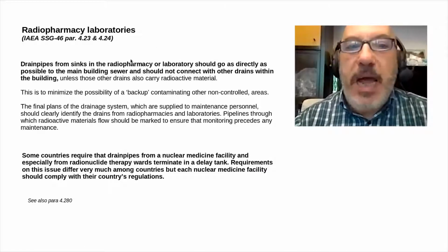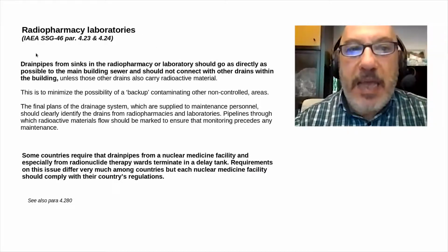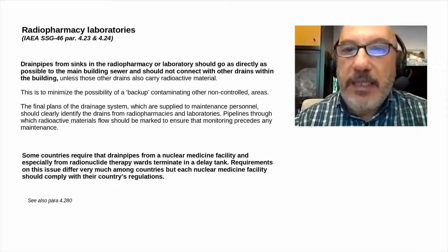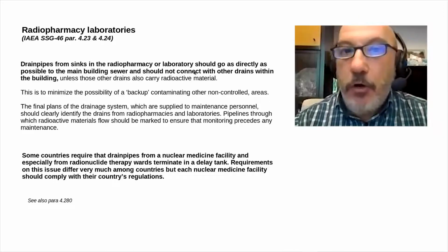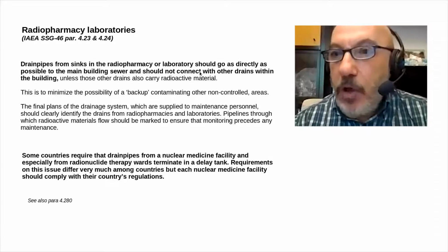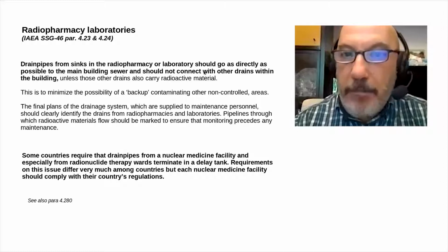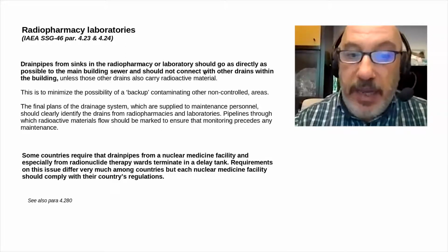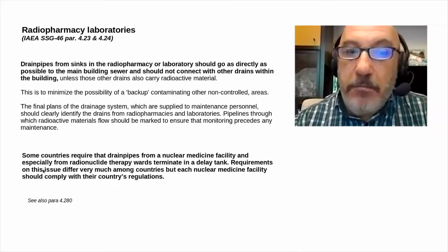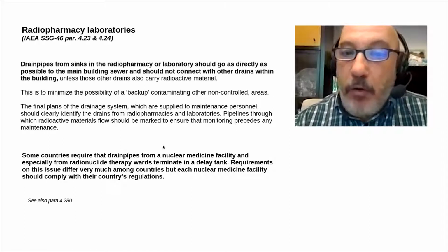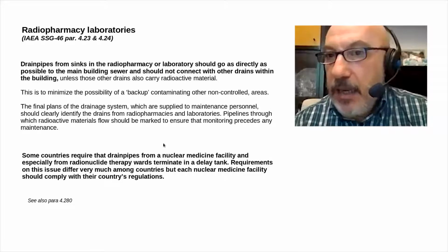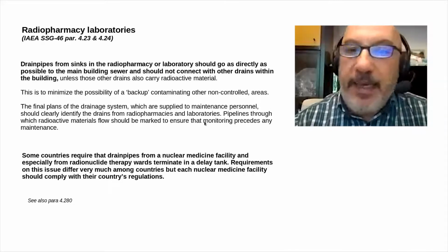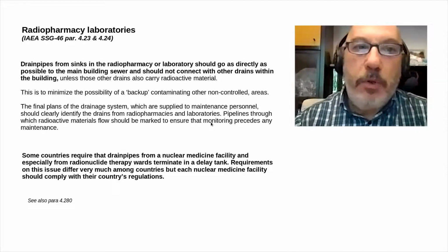As regards drain pipes, the recommendation from the IAEA SSG-46 is that they should go as directly as possible to the sewer in order to avoid any backflow, avoid any accumulation in the pipes itself. Nevertheless, in some countries, it may be necessary to collect all of this in specialized delay tanks. I will come back to this point later, speaking about therapy wards.